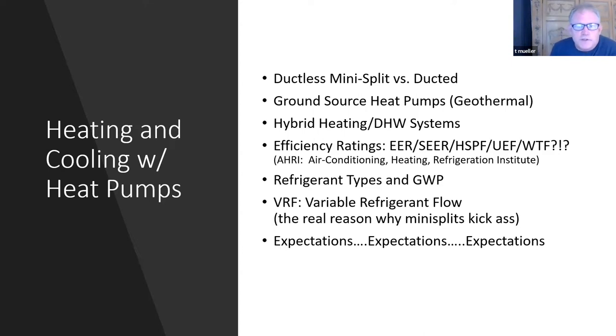Now, another thing I should mention about heat pumps that's different than gas furnaces, for instance, is that they really do operate best at capacity, most efficient at capacity. We're all familiar with efficiency ratings on gas furnaces, like a 96% efficient gas furnace. Well, it's 96% efficient when it's burning. It doesn't matter if it's going on and off rapidly or running for a long period of time, that's the efficiency of heat transfer.